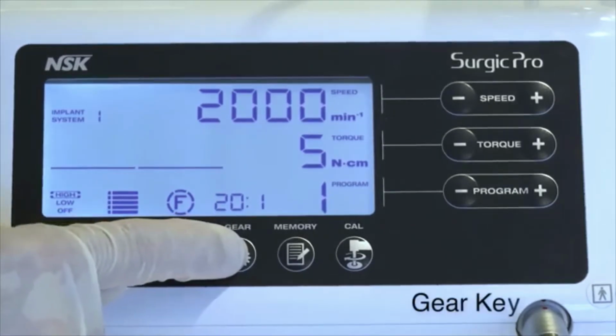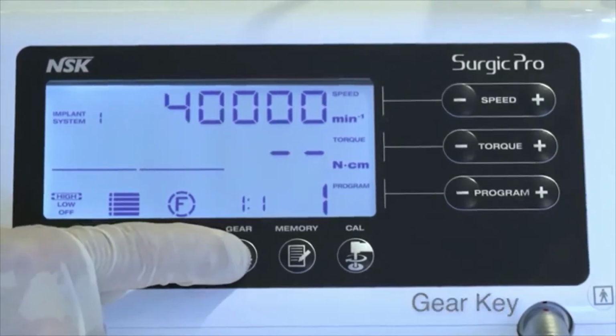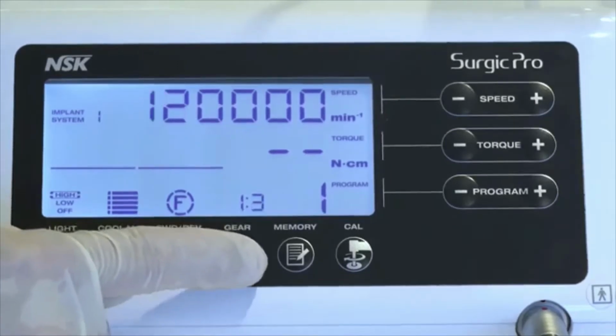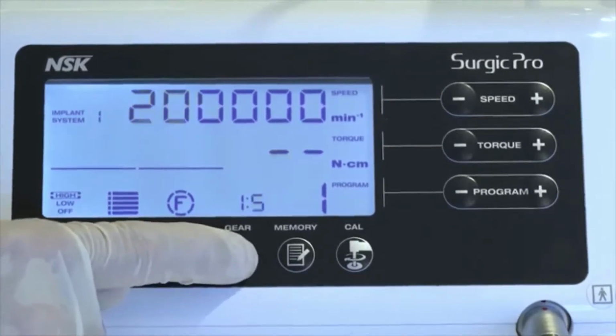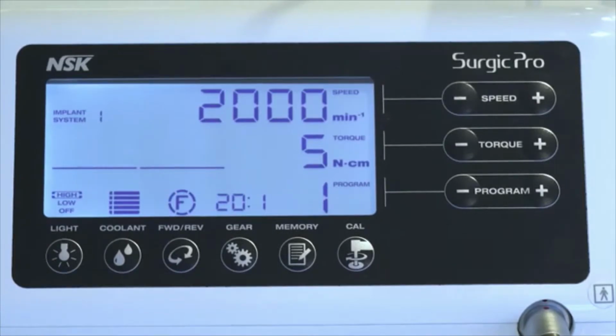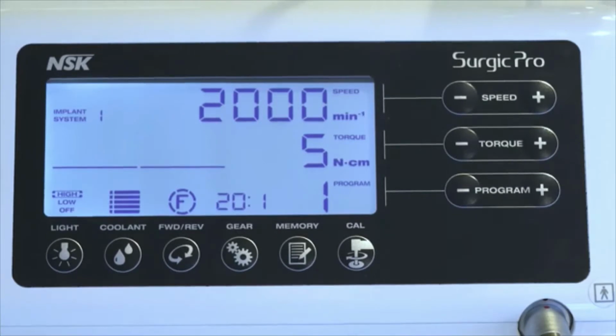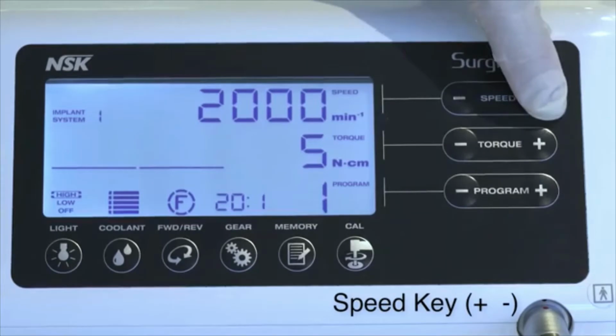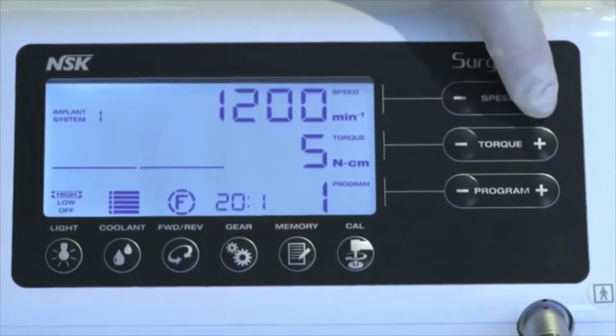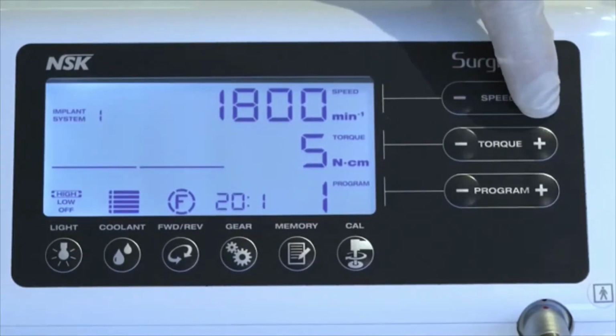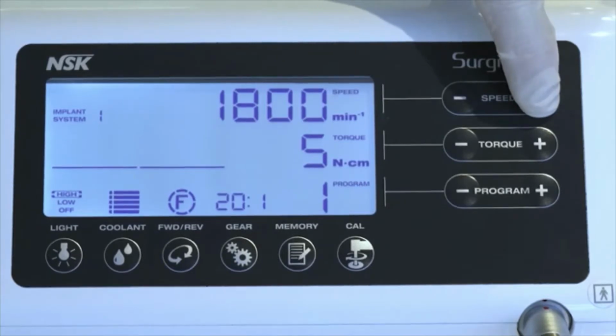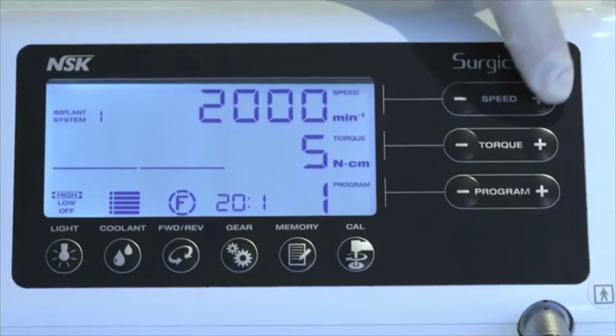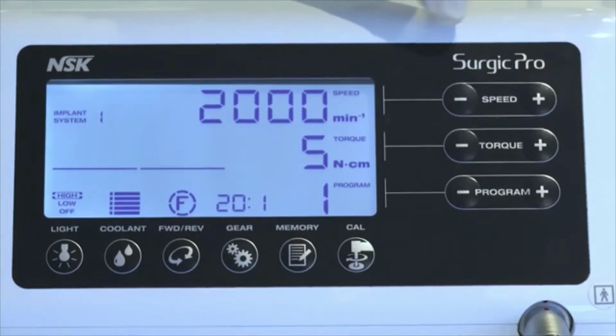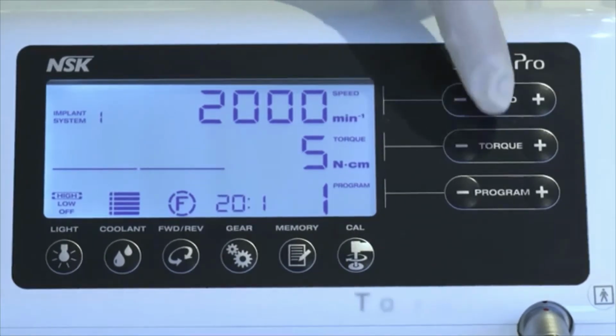Used to set the gear ratio of the attached handpiece before use. Press the same key until the LCD display indicates the correct gear ratio of the handpiece. For example, options 1 to 1, 1 to 2, 1 to 3, or 20 to 1. Used to set the micromotor speed. Press the plus key to increase and the minus key to decrease speed. Keep pushing the key to change the speed quickly. When the upper or lower speed limits are reached, an audible alarm will sound.